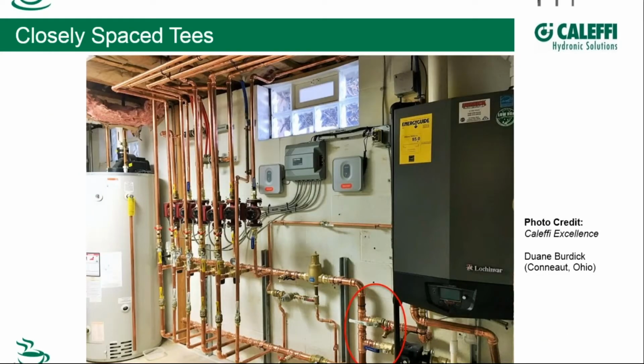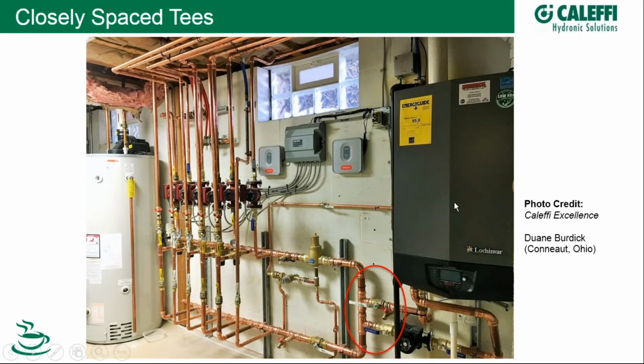So let's take a look at an execution of this. This was actually a photograph that I used last month from Ohio, and you can see we have a modulating condensing boiler over here. It might be 2, I think it's just 1. And we can see our primary pump pumping flow into our boiler, heating up the water. It comes out of the boiler, goes back out, and here's our 2 tees. Nicely connected together. Just think of the 4 times pipe diameter rule. Yes, that's abided by. And then out to our secondaries here, to our 6 or 7 secondary zone pumps, generously sized headers. So a very nice job doing a closely spaced tee arrangement.